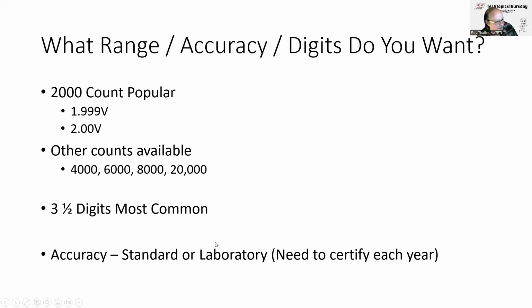Then there's accuracy - how accurate do you want it? If you want that accuracy, you'll need a standard, or you'll have to send your meter to the lab to get it recertified every year, which is quite expensive. So that's not recommended unless you're in the electronics business and need your meters calibrated every year.